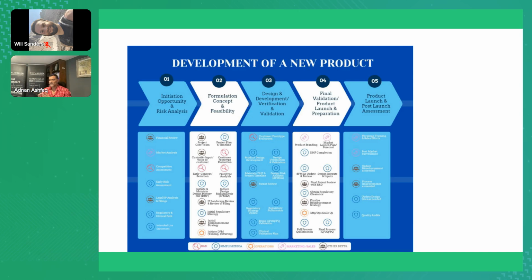is that our sales and marketing colleagues are very keen on getting devices commercialized and putting information in the public domain, which may have nothing to do with the intended use of the device. And guess what? That gets us into huge amounts of trouble. The regulatory authorities will be looking at information that's in the public domain. Any published material, anything that you may put on a website, anything on brochures, any literary information that could be in the hands of the public, the users, the patients, the clinicians, that then goes back to the intended use, which feeds into the instructions for use. And we'll have a look at this in a bit more detail now.